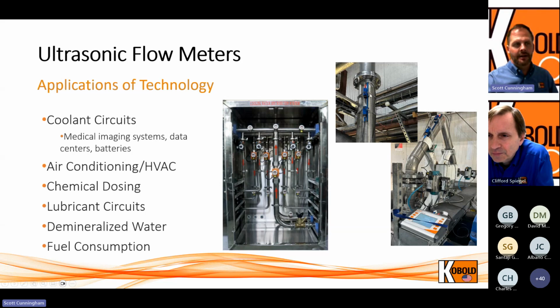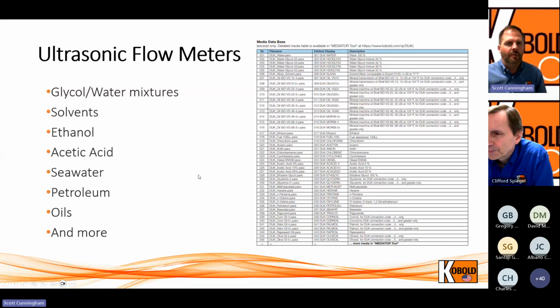And then on the right-hand side, you're looking at the clamp-on ultrasonic technology. You've got a processor here, the user interface for our portable setup, and then your transducers. There's different sizes. Those can be placed on the pipe, and the software walks you through based on your diameter and wall thickness and material type. It'll tell you how far apart to put the transducers, how to do your setup, and then you can start measuring flow without breaking into a pipe. So again, some of the advantages that we'll touch on here as we get into it more.